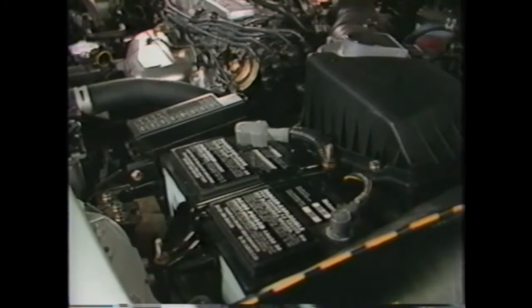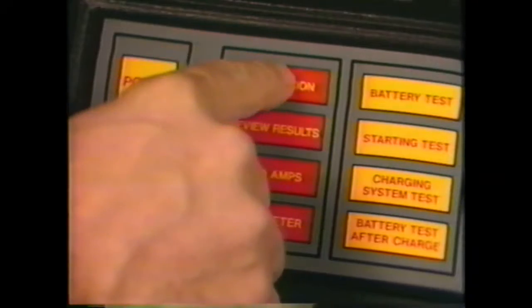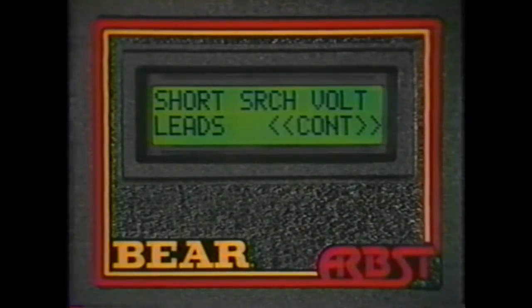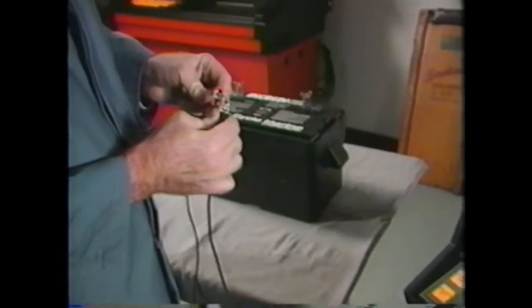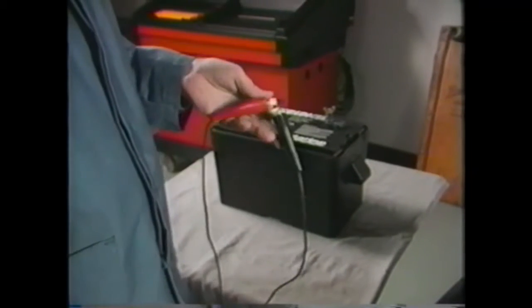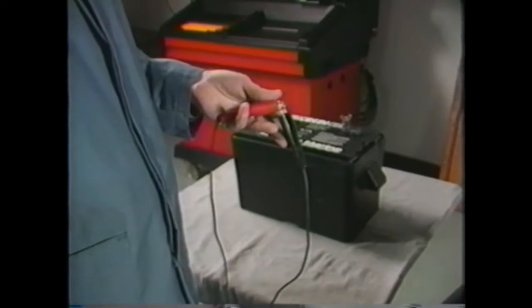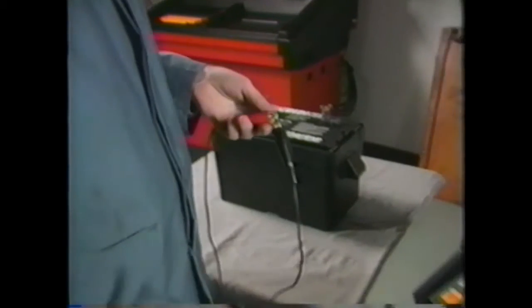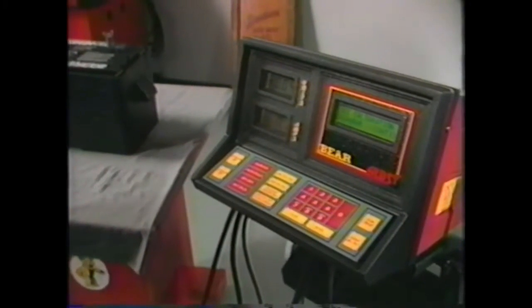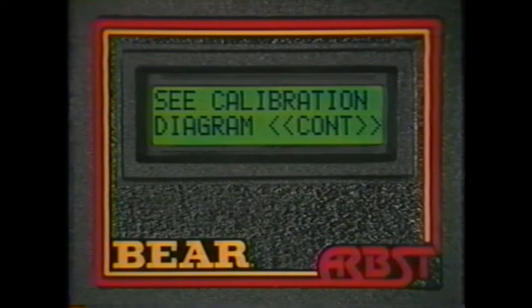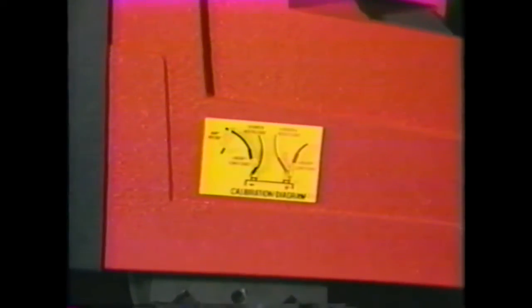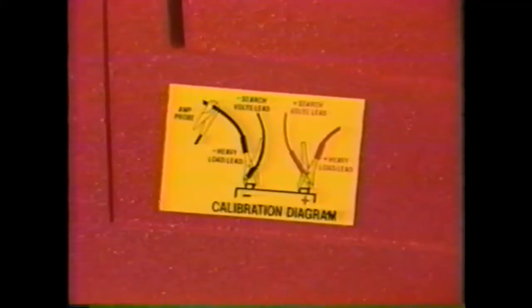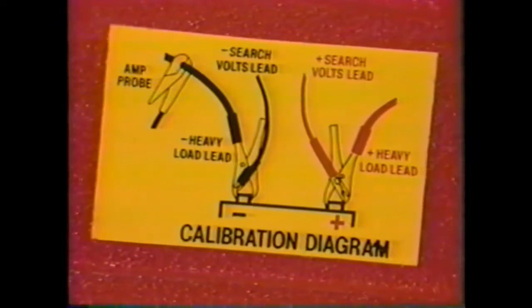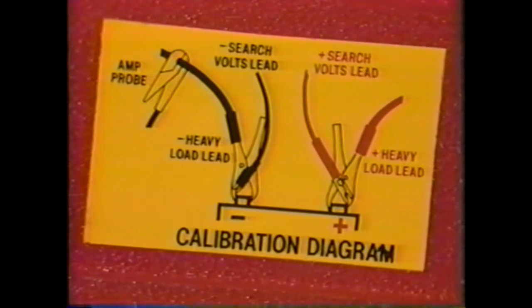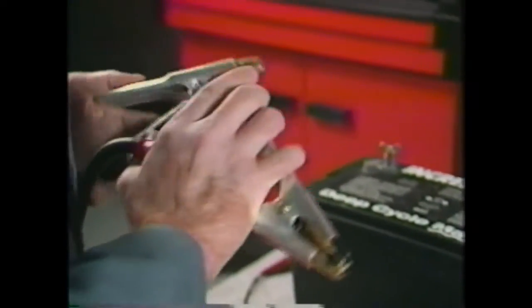The procedure is simple. Press the calibration key. The display will say Short Search Volt Leads. To short the search volt leads, clip them together so that the metal clips are in complete contact with each other. Press Continue. The display will then advise you to see calibration diagram. There is a calibration diagram on the tester housing which shows you how to connect the test leads for the remaining calibration steps.